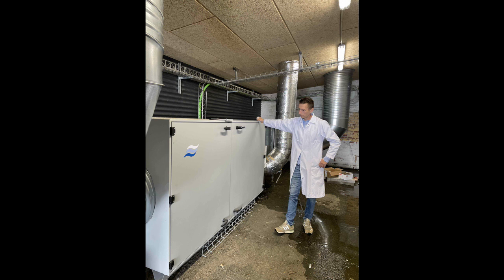Most of the time, we're trying to help a client solve an icing or a misting issue inside a store rather than on the fridge system, and the energy savings are largely a secondary objective. However, in some blast freezer applications where dry air has been introduced onto the evaporators, the period necessary between defrost cycles has been extended from once a week to once every 3 months. And as the dry air can be left on during the defrost cycle, the time it took was reduced from a whole day to just a few hours. So the potential energy savings there and productivity improvements are significant.